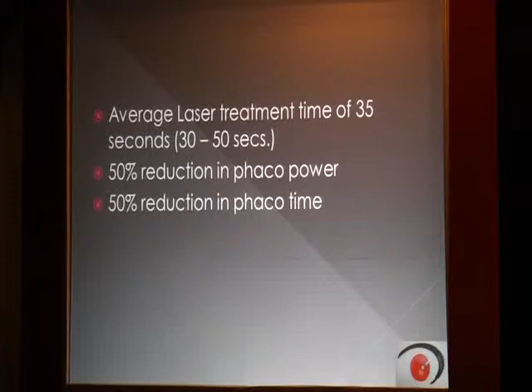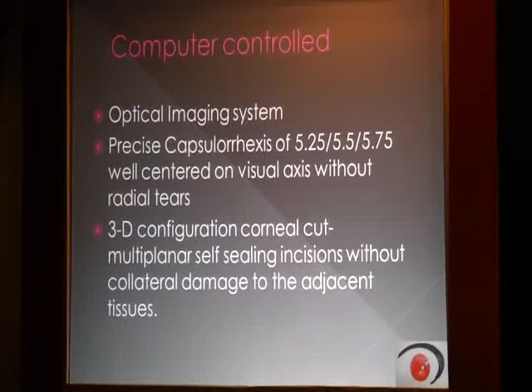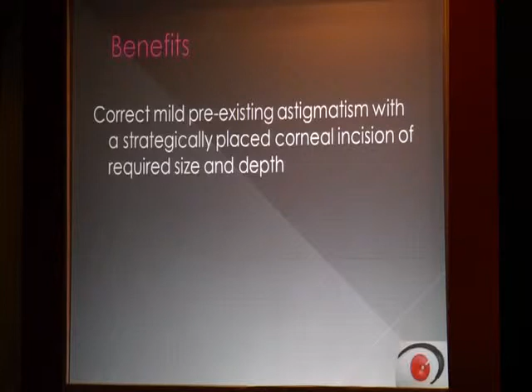Average laser treatment is 35 seconds. It reduces the phaco power by 50% because all the nucleotomy, the division, is already done. You don't have to hold, just take the nucleus fragments out. And there's a 50% reduction in the phaco time. And you can have the precise capsulorhexis of 5.25, 5.5, 5.75, and there is a 3D configuration corneal cut, which is so well self-sealing that you do not even require hydration of the side ports or the main port. Also, it corrects the mild pre-existing astigmatism with strategically placed corneal incisions of required size and depth.